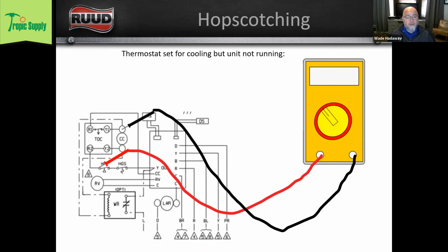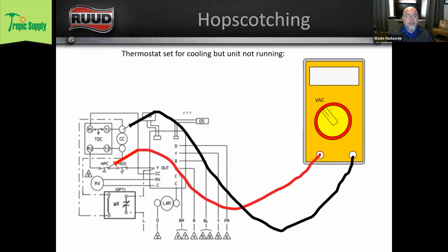The next thing I'm going to do is hopscotch to the next switch, which is our high pressure control. Am I getting 24 volts through the high pressure control? You can see that I've got 0 there. So I don't have 24 volts through my high pressure control. And what that tells me is that the high pressure control is open, because if you go back and look coming into that high pressure control, I've got 24 volts. So that switch is open. I've got 24 volts potential sitting there waiting for that pressure switch to close so that those electrons can continue to flow, go through my contactor coil, and then back to my contactor common on my board.